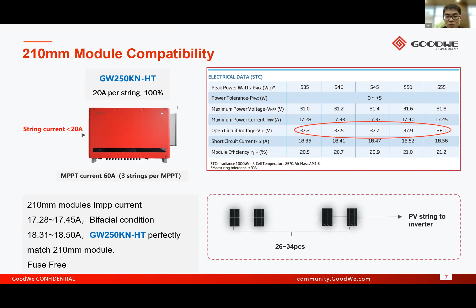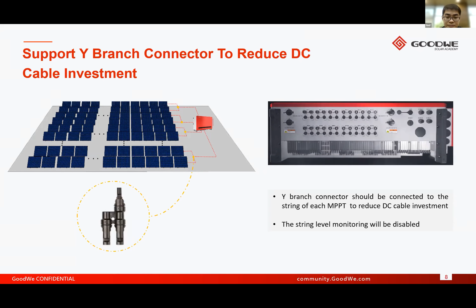Next slide is about the Y branch connector. We noticed that some projects are using this Y branch design to lower DC cable investment. The parallel connection is accomplished by joining the positives of 2 strings together as well as the negatives of each string together. Then the combined current is transported by a 6 square millimeter DC cable to our inverter. In this scenario, the combined current can reach more than 25 ampere. Note that the 2 models can still support this large current if each MPPT only connects 1 string, but string level monitoring will be disabled in this situation, while MPPT level monitoring still exists.